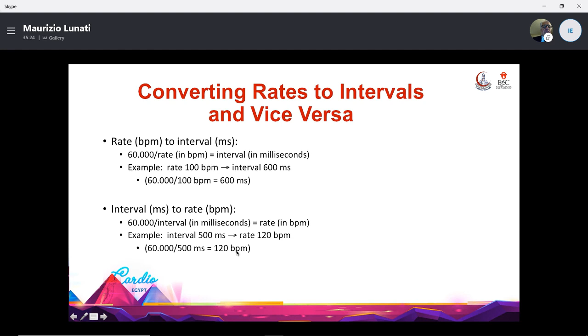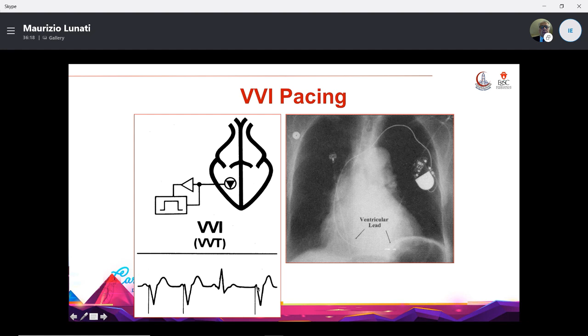This is the first mode of pacing, VVI pacing: the chamber paced, the chamber sensed, and the mode of functioning of the device, inhibited. The lead is in the ventricle. You can see the chest X-ray with the device and the catheter, which is put in the apical portion of the right ventricle. And this is a small example of how an electrocardiogram of ventricular pacing can look. We have 2 beats preceded by spikes, a spontaneous beat, and the pacemaker is inhibited, and then the return of a new ventricular pacing beat.